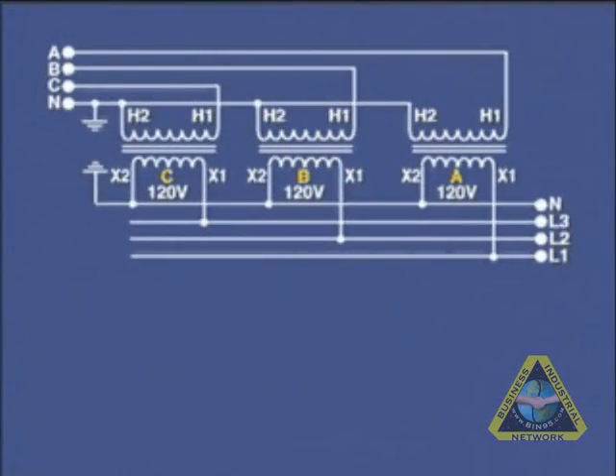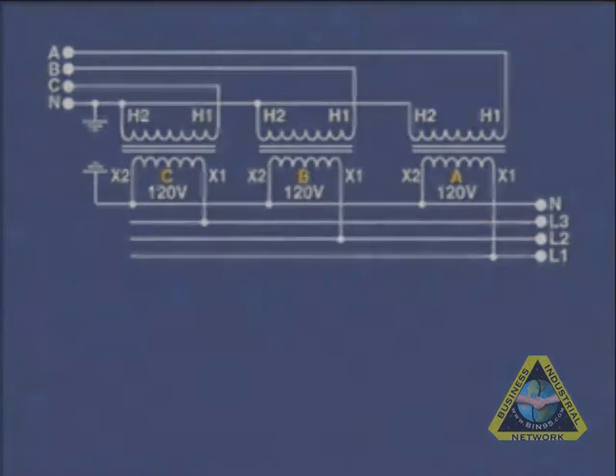Let's go over this transformer wiring to make sure that we have it wired in a Y configuration. Tracing from line A to the first coil's H1 terminal, we go through the coil to H2. This H2 terminal of the first coil goes also to the neutral.